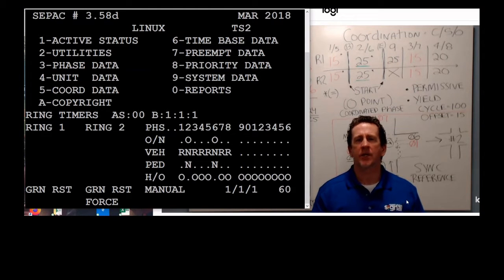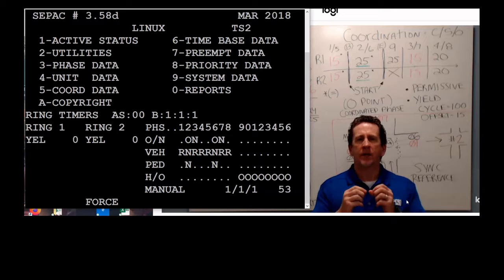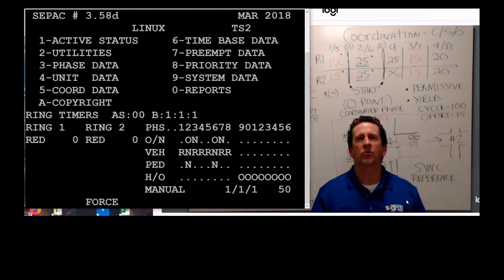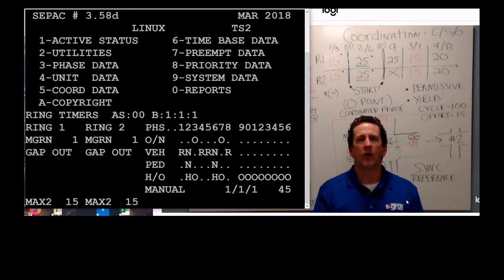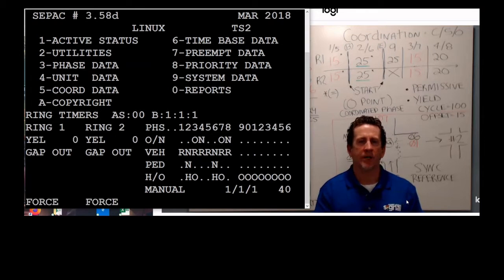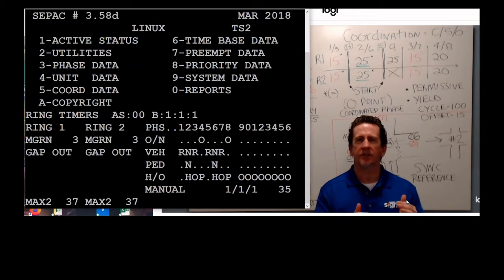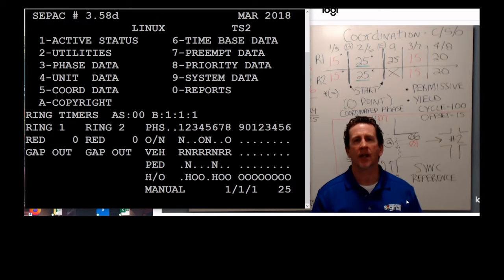Today we're doing coordination and time-based programming. I'm going to not be as detailed because this is about programming the data into the controllers, as opposed to a class on coordination. A lot of novice people are here so I don't want this to go off the rails like a coordination class can. I'm going to go over the basics, the generics. I touched on it a little bit last week and I'll show you how to implement the coordination data into the controller, because that's pretty critical and a lot of times it doesn't happen.